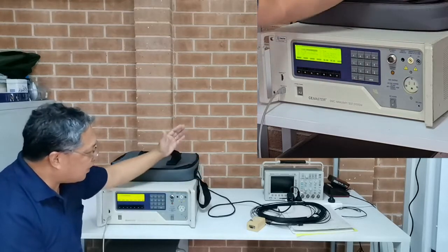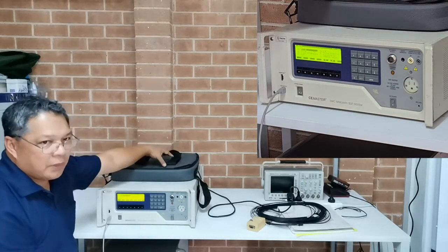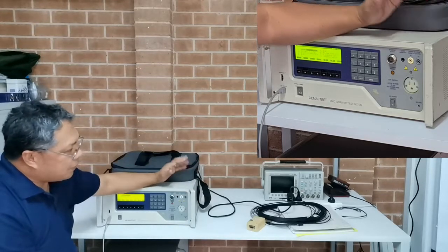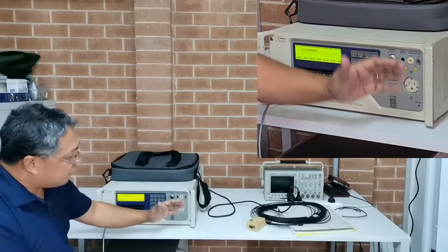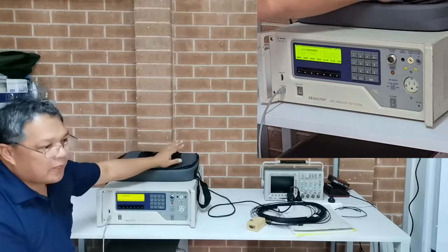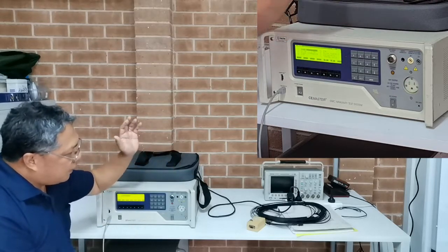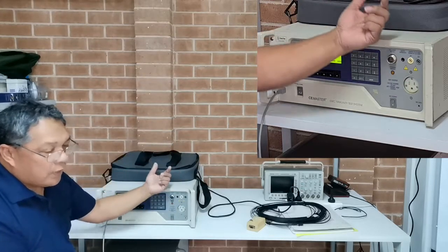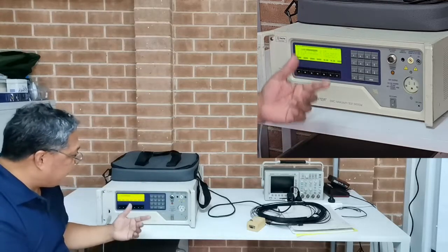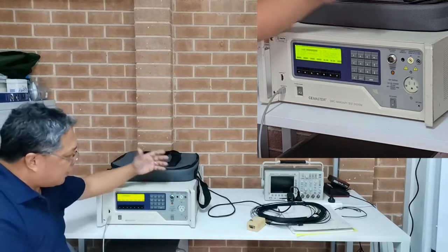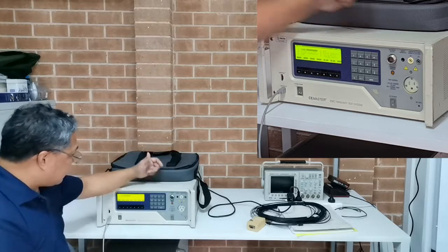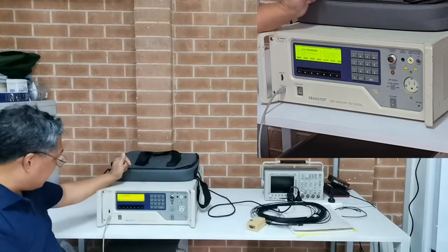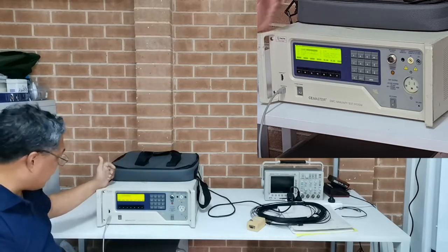So the best thing I can do is to build a separate decoupling network. So what does a decoupling network do? This one has an internal decoupling network. That decoupling network prevents the surge from going back into the main supply, and it only allows the surge to go into the EUT. So that's what decoupling networks are used for. That's not a problem for the decoupling network, so we can build that one.